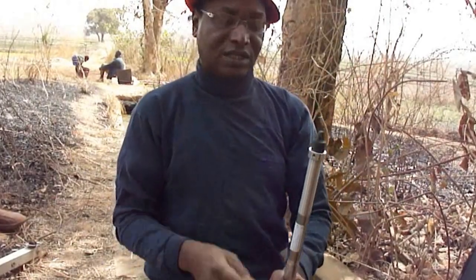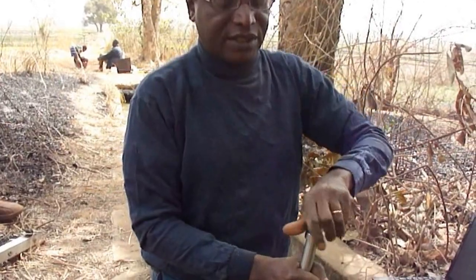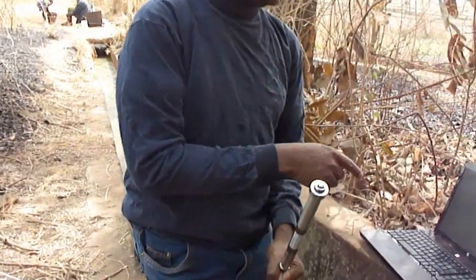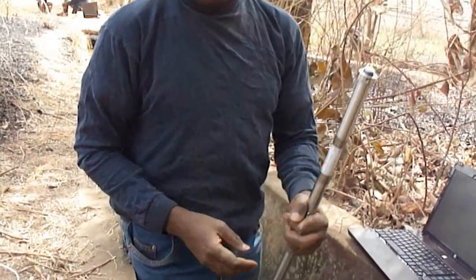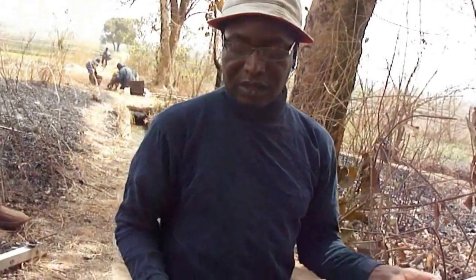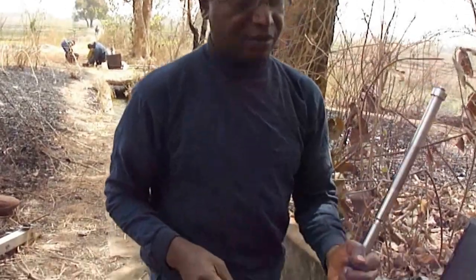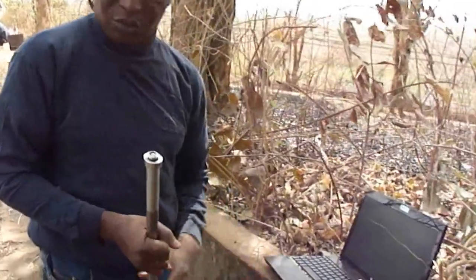You put this stick, and then you connect this side — the top of this e-water level — to a computer in order to program or schedule at what times and at what interval the measurements are made. This is done by connecting this side of the diver to the computer.